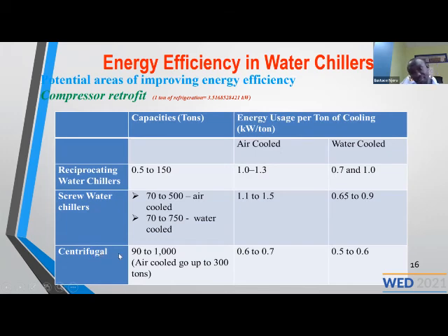At the same time, for the centrifugal, don't reduce their speed below 20% of the rated speed. They are efficient at above 80% speed. So if you discover that you are going to reduce the load below that, you should either use a screw or use a relatively small centrifugal compressor. Water chillers come with several compressors, so you can have a system of switching from one to another.